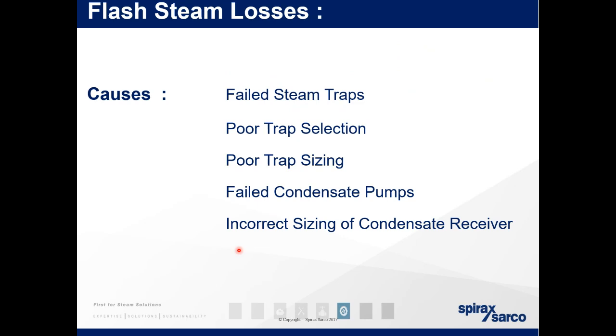In any other position or any other pressure differential, the trap won't function properly. So you either might need a bigger one. 4.5 would be our smallest. So say you have a 10 bar differential pressure, you'd go for the FT-10. So, correct selection of equipment.